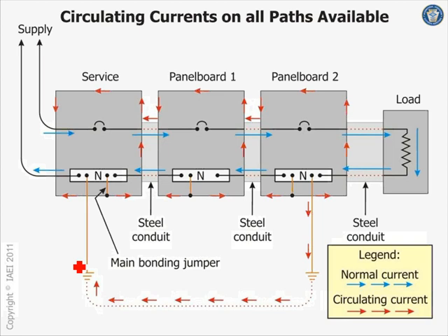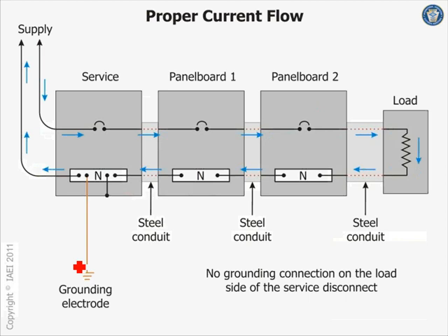Well, safety. You could have plumbers coming and working on a water pipe, and they open the pipe and it arcs, because it's carrying current. So that's a hazard. If you have flammable things, or it's a hazardous location, that arc could create a fire. Your low voltage guys work on low voltage equipment and get shocked by the coaxial under normal operating conditions. That's what you will avoid. You avoid this by what? By only bonding the neutral on one side. Any comments, guys? Yes, sir.